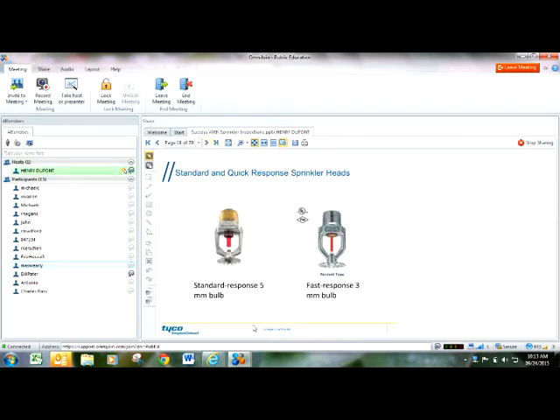So you might ask yourself, how do I tell the difference between a standard response sprinkler head and a quick response sprinkler head? And that's really easy. They're both glass bulb sprinkler heads, and you might assume that they're identical. Well, the 5 millimeter fat bulb is a standard response sprinkler head, and the 3 millimeter bulb is a quick response sprinkler head. They can be in the same building, but they can't be together in the same compartment, whether a room, a large room, or a small room. If you see these two sprinkler heads together, that would be a deficiency, and the standard response sprinkler head needs to be changed out to a quick response or vice versa. That's pretty low-hanging fruit when you're on an inspection.